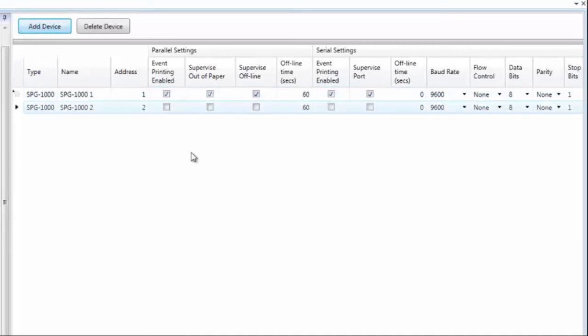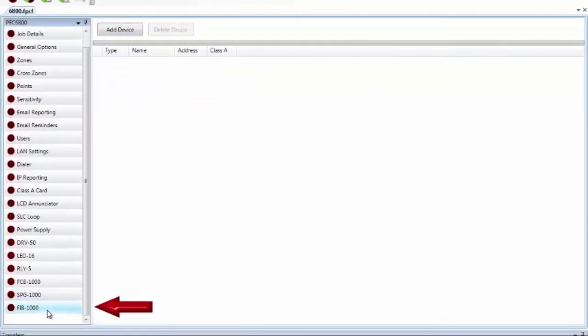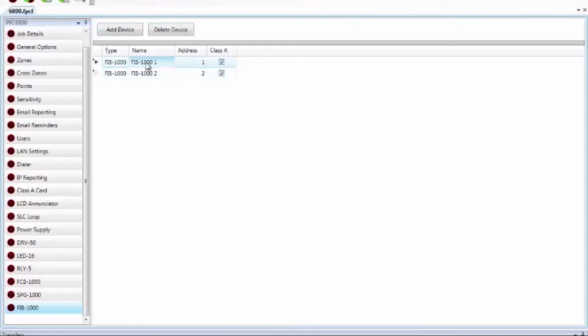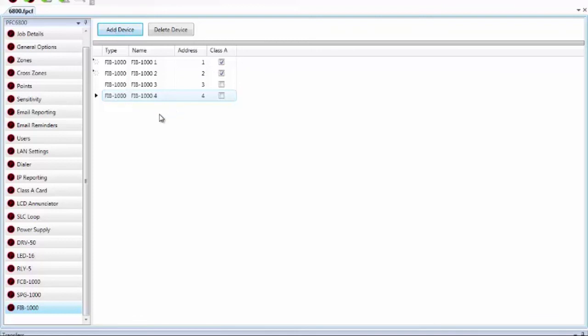Moving to the FIB-1000 — this is the fiber interface bridge. To add an FIB-1000, click Add Device. FIB-1000s must be installed in pairs, so click Add Device again to get two. They need to be addressed consecutively — the default addresses are 1 and 2. If your fiber connection is going to be Class A, select Class A. You can name these devices for troubleshooting purposes. To install another pair, click Add Device again. You can have a total of 30 FIB-1000s, or 15 pairs, installed on every system.